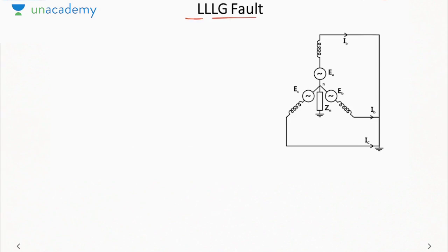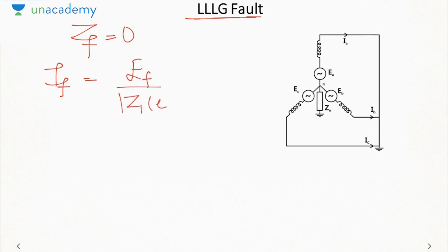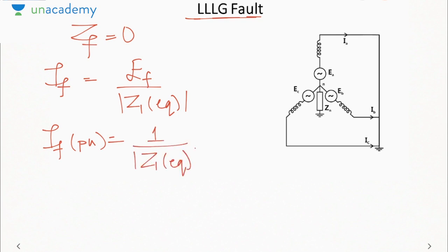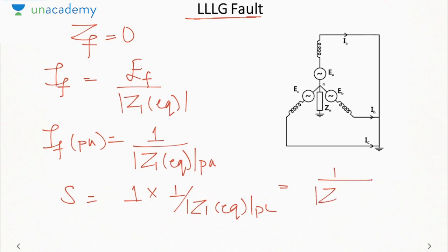Next, in case of a triple LG fault, this is the other type of symmetrical fault. Here what is happening is just that ZF has gone to 0. So what will be the fault current? It will be EF by mod Z1 equivalent. What will be IF in PU? It will be 1 upon mod Z1 equivalent in PU. So what will be S? That will be 1 into 1 upon mod Z1 equivalent, so that is 1 by mod Z1 equivalent in PU.